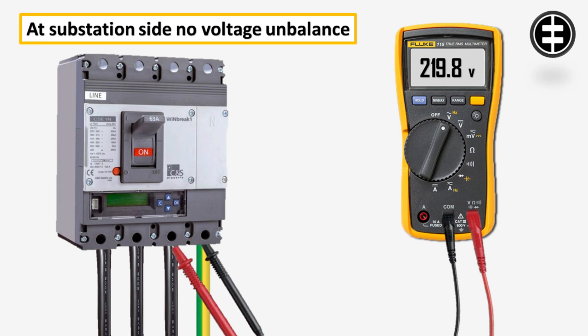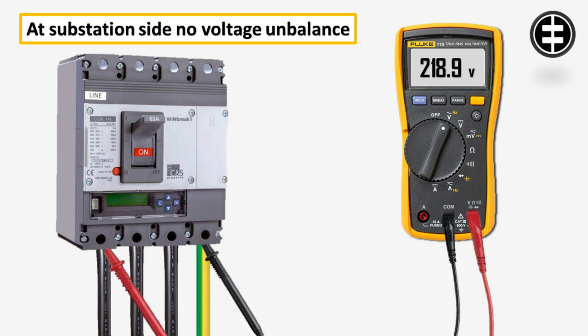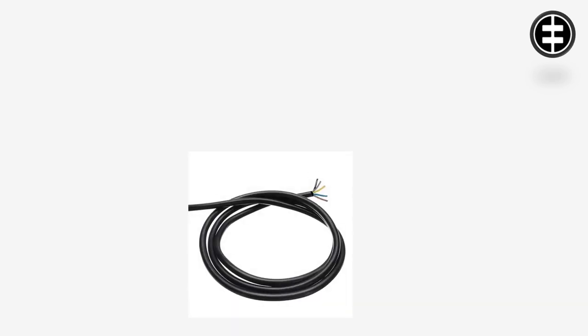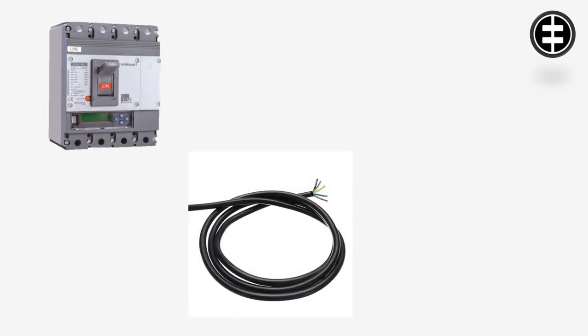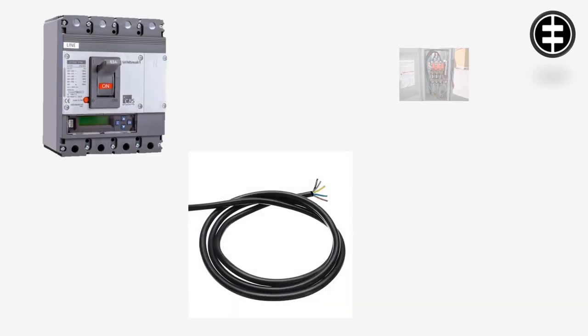If there was no unbalance at the substation side and the unbalance was found only at the motor side, that means you need to check your cable and cable connection points, isolators or breakers in between, and connectors.